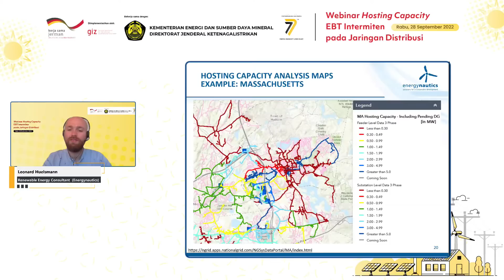This is really what I wanted to share with you. Hosting capacity assessments are still a relatively new area. The Californian electricity regulator only quite recently approved a resolution to enforce and require these hosting capacity analyses in the interconnection evaluation process, with the main goal to speed up interconnection requests and provide greater visibility to PV developers on whether they are likely to get connected. This is still a little bit in process; I think it may have been approved or put into regulation by now. My recommendation is to follow these developments in California closely, because I think they are highly applicable and relevant for Indonesia to learn from.